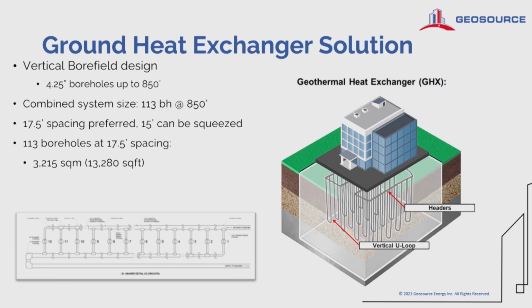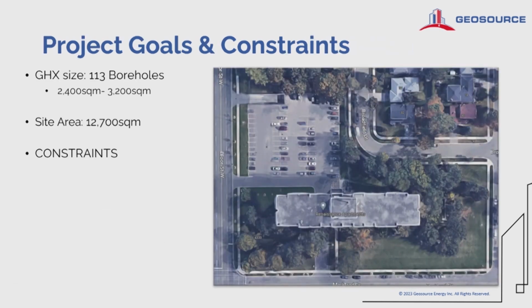Typically, GeoSource installs vertical bore fields for ground heat exchanger design. This is because we find that in our client base, space is the number one constraint. Our rigs allow us to drill boreholes up to depths of 850 feet. And for this particular project, the required size would be 113 boreholes at 850 feet. We typically prefer to space boreholes of this depth at 17.5 feet but we can squeeze down to 15 at some cost to efficiency. So for reference at this site, at our preferred spacing, we're looking at 3,200 square meters of surface area required, but we can squeeze into about 2,400 if necessary.